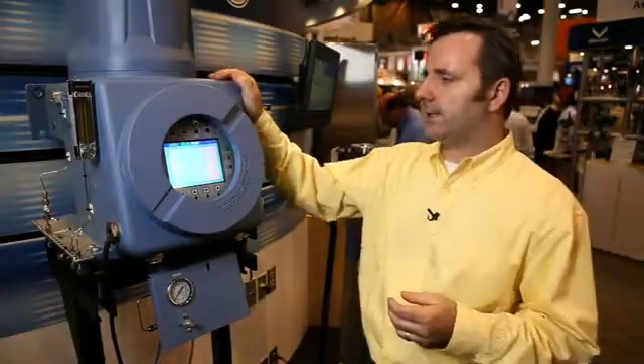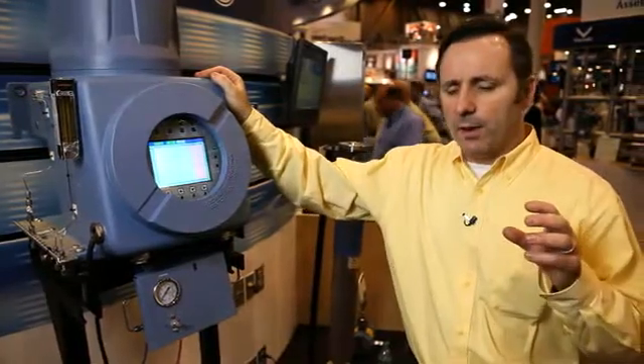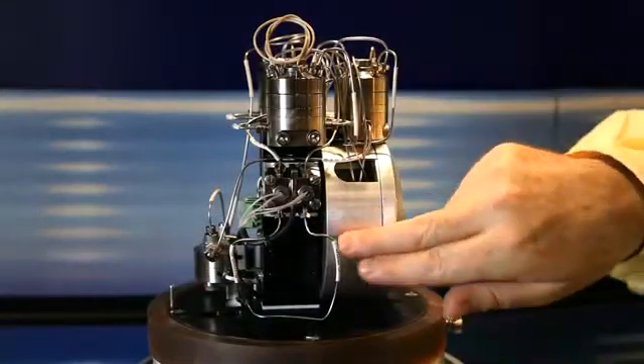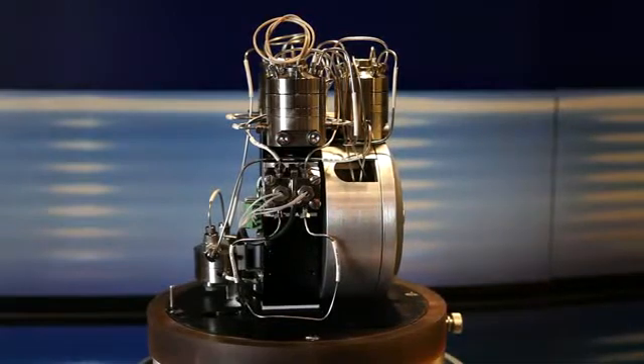What we do with the 700 XA is we take our C9 plus measurement and we expand it to include methanol and water. And the advanced electronics allows us to put two analytical flow paths through a single thermal conductivity detector.